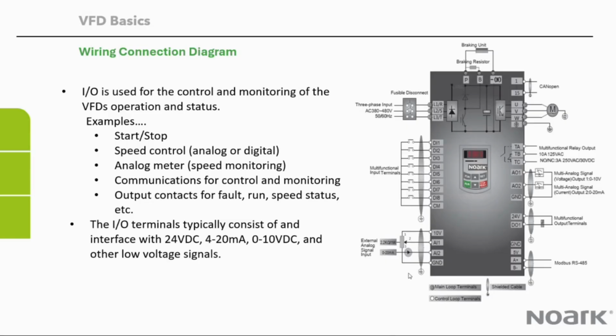The analog inputs could be a potentiometer, which varies the speed of the drive if you tell the drive to look at that analog input. Let's say a potentiometer here is wired to analog input 1. It takes the 10 volts and varies that from 0 to 10 volts, and that makes the drive go from 0 to full speed.